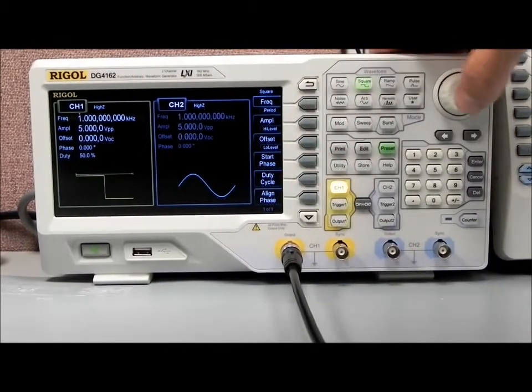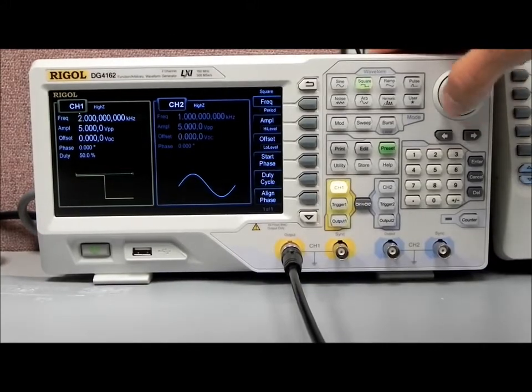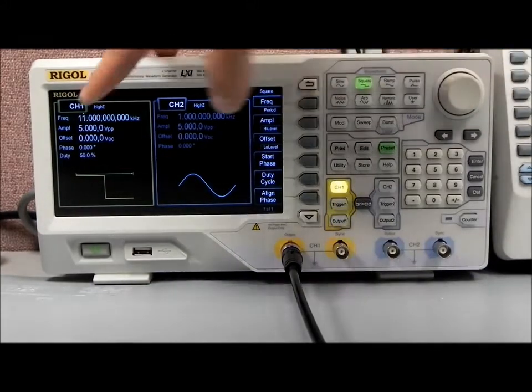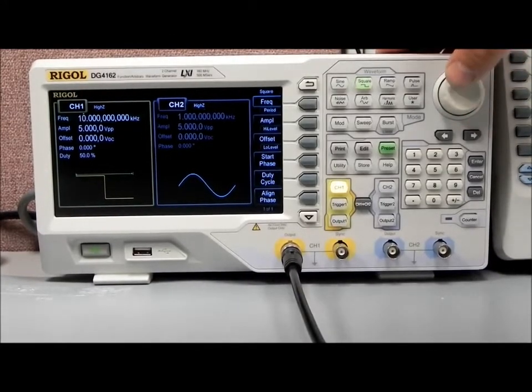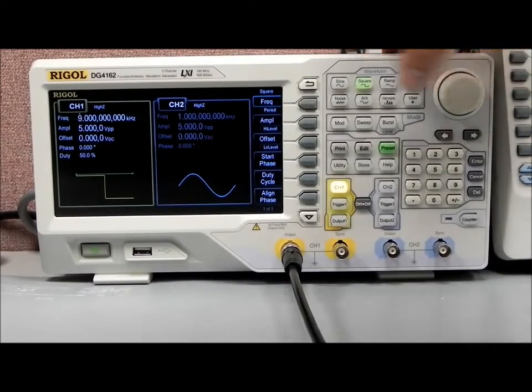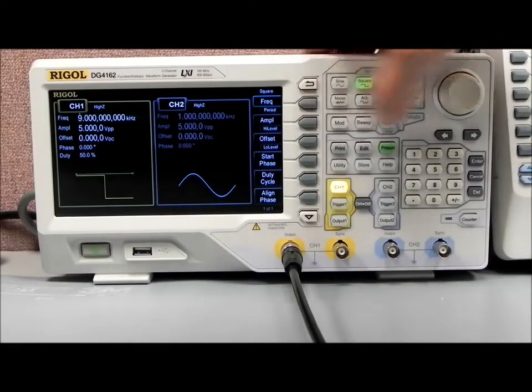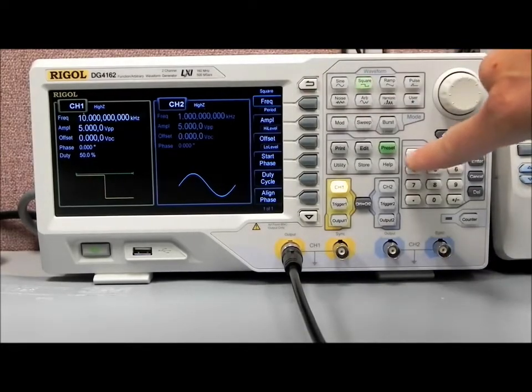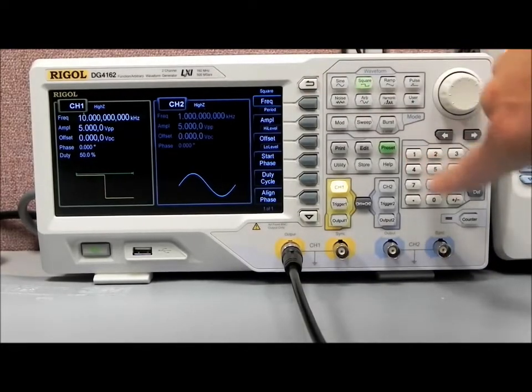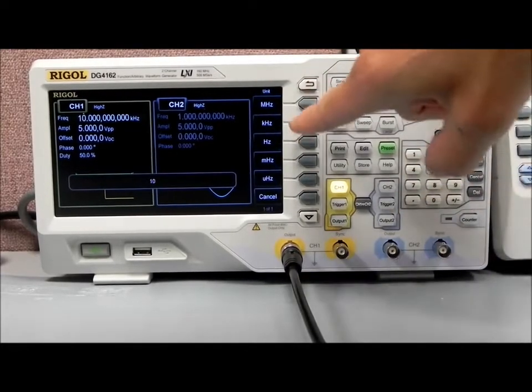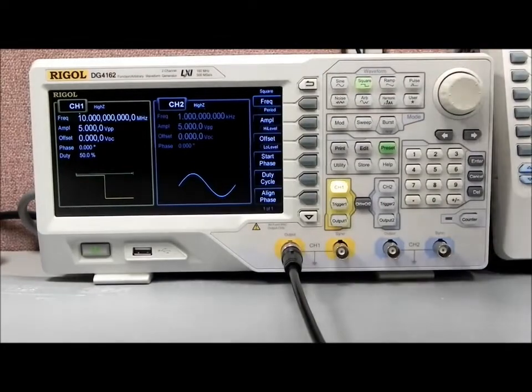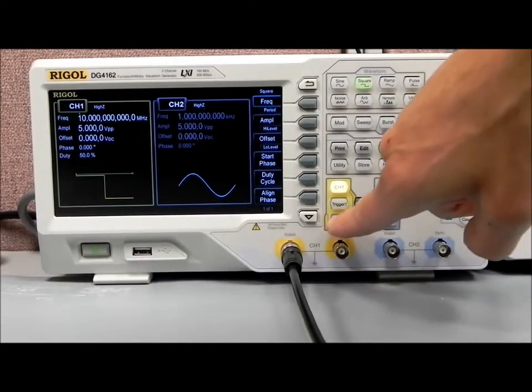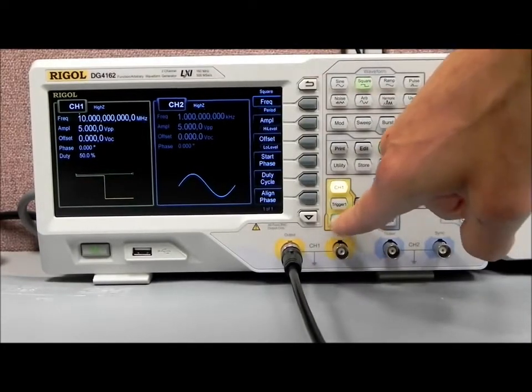Let's go to frequency. There are a few different ways to enter that information: we can use a scroll wheel to increase the frequency, or we can use the actual keypad — for example, entering 10 MHz. And now let's turn that output on.